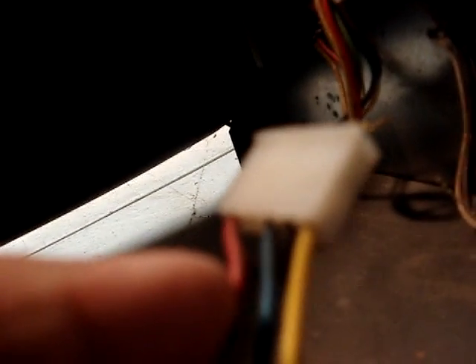So if we look at the plug here, pin 1 is the yellow connector, and the pin 2 right next to it is black. Well, on my Asteroids monitor, the G05, I just looked in there, and black is on pin number 1, and the yellow is on pin number 2. So all I'm going to have to do is reverse the yellow and black positions, pin 1 and pin 2, and that should straighten it out. But I just wanted to point out that in that documentation, this connector is labeled wrong. They got it labeled as P700, and it's supposed to be P701. So let's go ahead, and all we have to do is pull these two terminals out and switch them over, and we should be good to go.